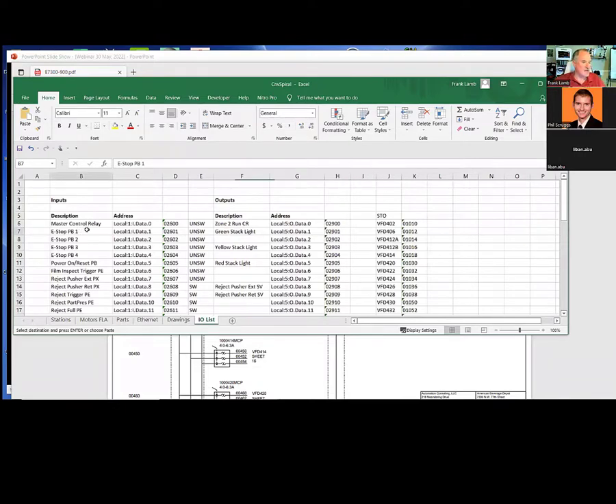What I usually do whenever I make an IO list is start with the safety stuff. In general, you're going to have a master control relay and some e-stops, things like that, and a power on reset button, usually the green button on the front of the panel. So that's these things right here, and these numbers come from the drawings—that's kind of where I usually start on my IO list.